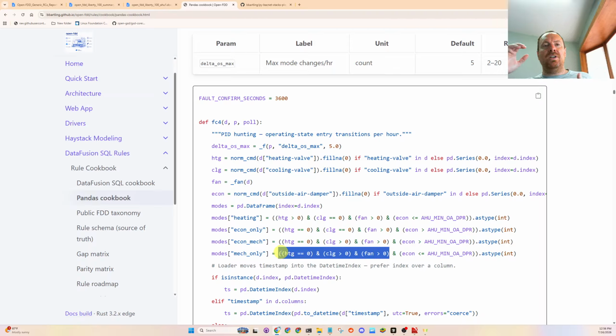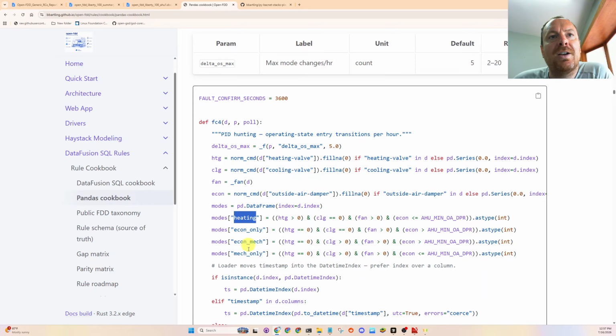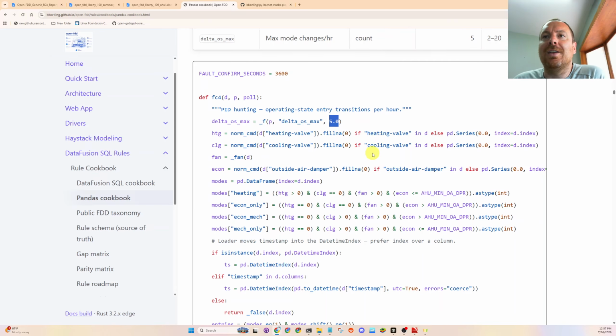So we're running data through these functions, and the function is telling us that there's hunting occurring here, by how often the air handling unit is oscillating between these different modes. It's all defined by Guideline 36. There's a lot that you can tell by the heating valve, cooling valve, fan speed command, and the outside air damper. As they're going like this, those are different modes that the air handling unit would be operating in. And Guideline 36 defines stage changes of 5. I think it's actually 7, but that seems like an awful lot to me as the maximum stage changes per hour. It should only be like 1 or 2, I think.